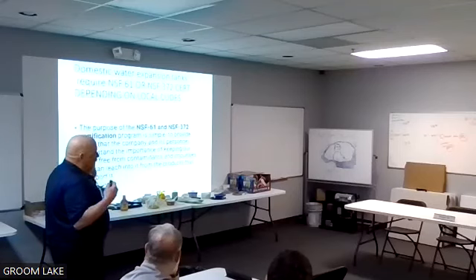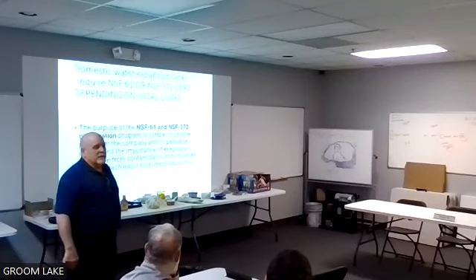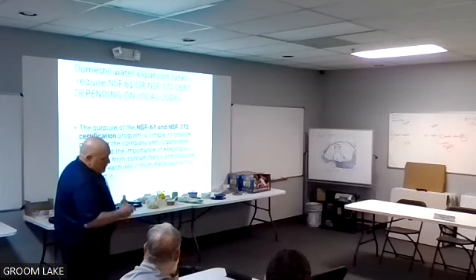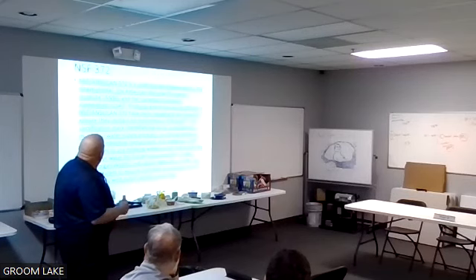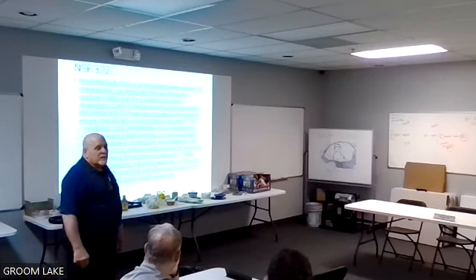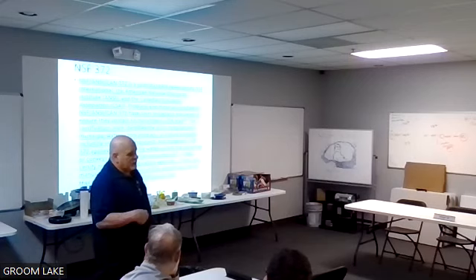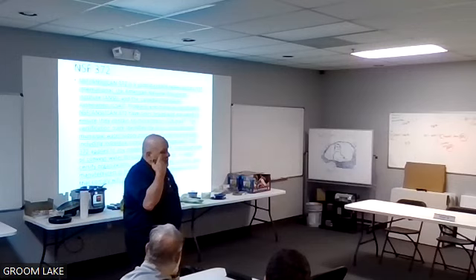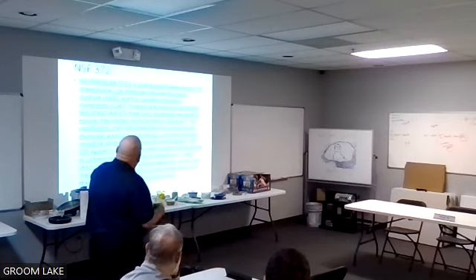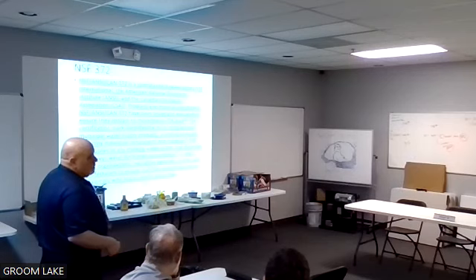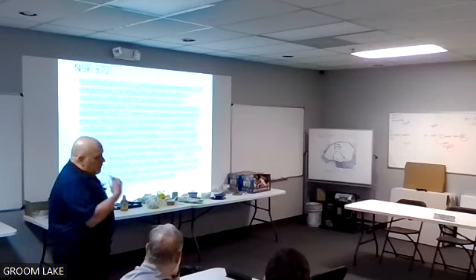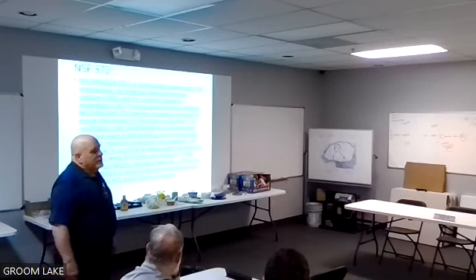They just said this is a way to make sure there are no contaminants in the drinking water. NSF 61 and 372 are very similar. NSF 372 basically says I'm allowed 0.25% lead. Some jurisdictions will recognize NSF 372. Other jurisdictions want NSF 61, which is much more stringent. And this will just tell you, if you want to read through there, that it applies to drinking water and for human consumption. And it all comes down to one thing: low lead. And that's why they're trying to replace all the lead pipes in a lot of these cities.